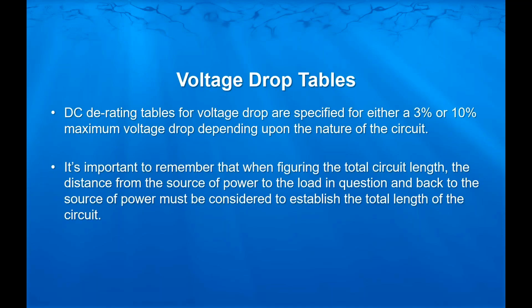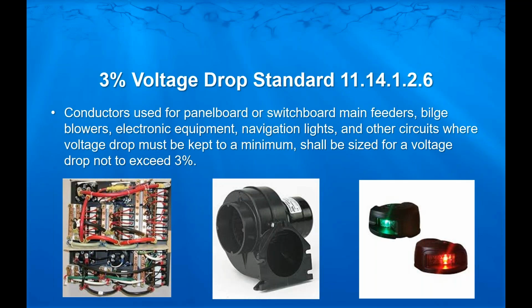It is very important to remember that when figuring the total circuit length, the distance is from the source of power to the load in question, your device, and back to the source of power. You've got to consider that to establish the total length of the circuit. The length of the circuit is not the distance from the battery to the light or the AC panel to whatever it goes to. It's twice that distance. You've got to calculate the entire loop, the entire circuit is the total circuit length.